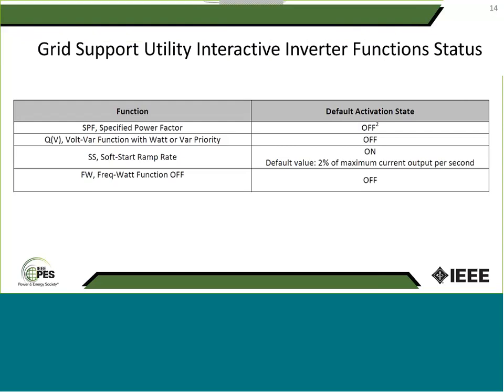There are other functions under 1741 SA that you see here that for now are off, like specified power factor, volt-VAR function, watt-VAR priority, and all that. So these are off for now. The only thing that is on is the ramp rate. We picked 2% of maximum output per second as the ramp rate. But again, we're working on the rest of the requirements under 1741 SA.